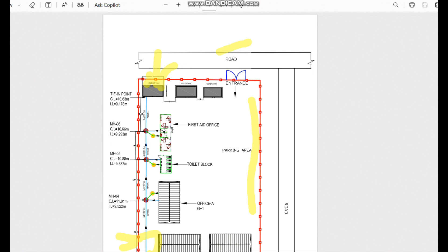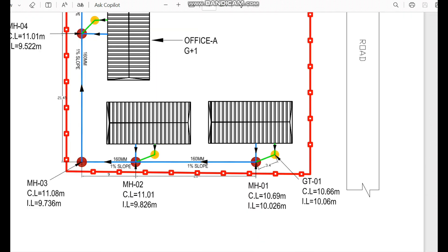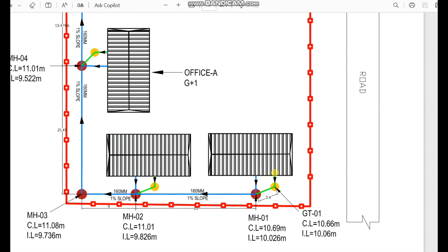As a mechanical engineer, the first step is: for all the buildings, the wastewater from the kitchen sink and wash basin is collected separately, which I indicated in green color. Similarly, for the soil water from the water closet, that is collected separately, indicated in blue color. The same concept is repeated for all buildings. Wastewater from the building is first discharged to a gully trap, and from the gully trap it is discharged to the manhole. But soil water is directly discharged to the manhole.